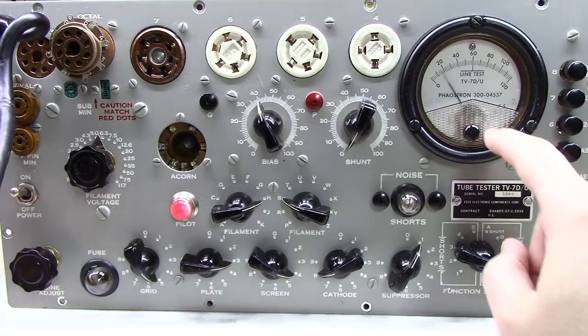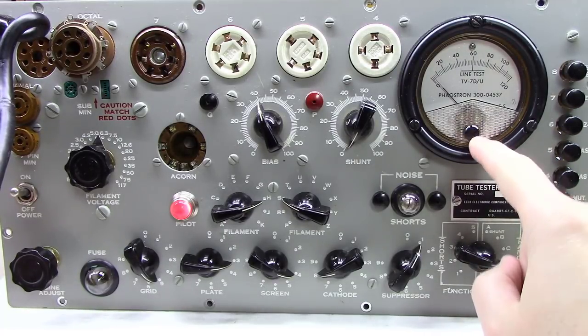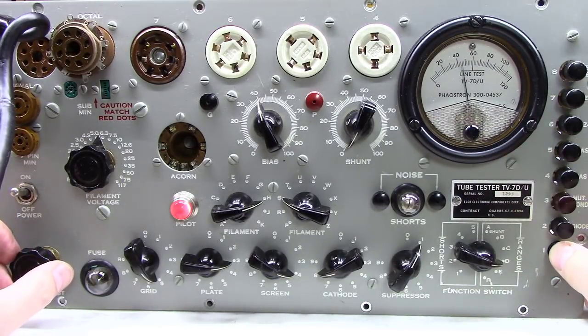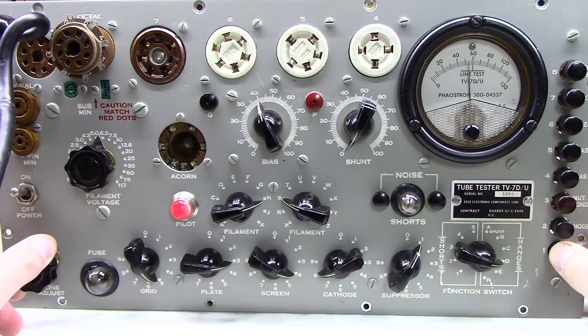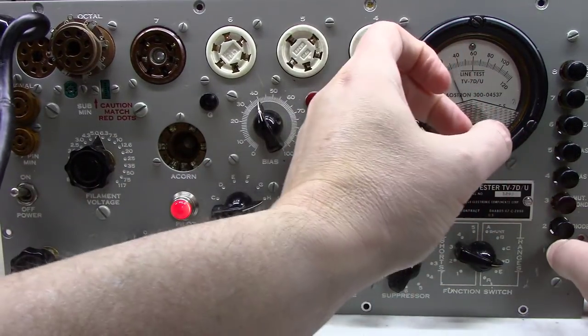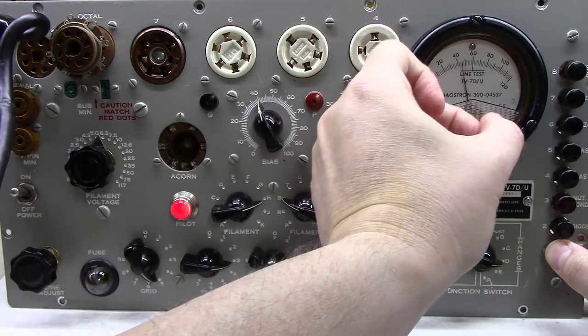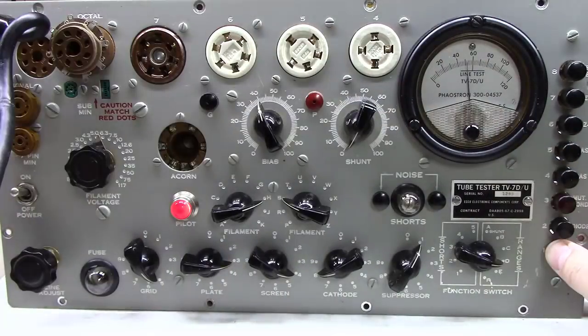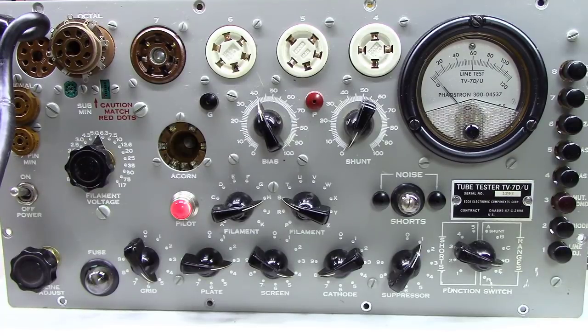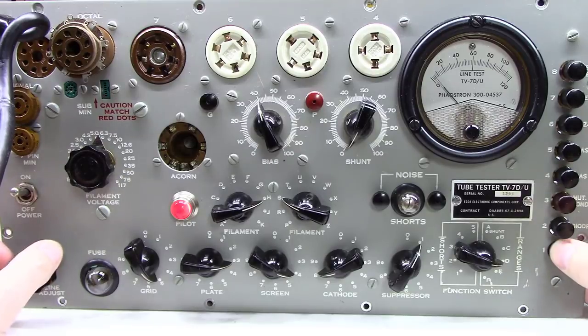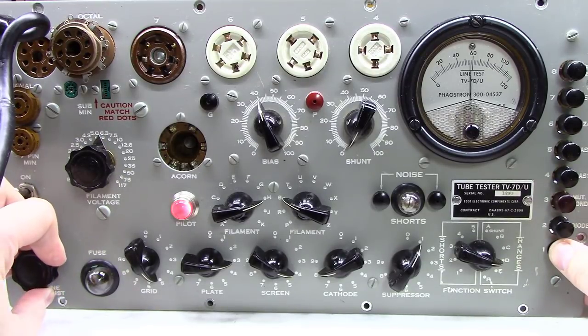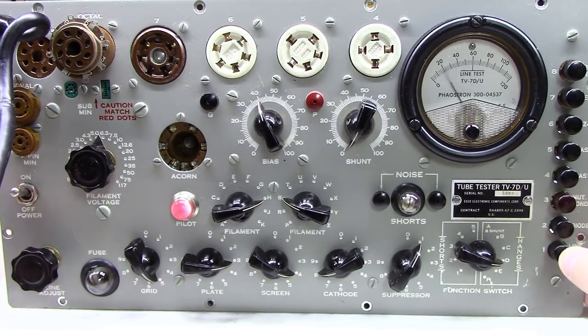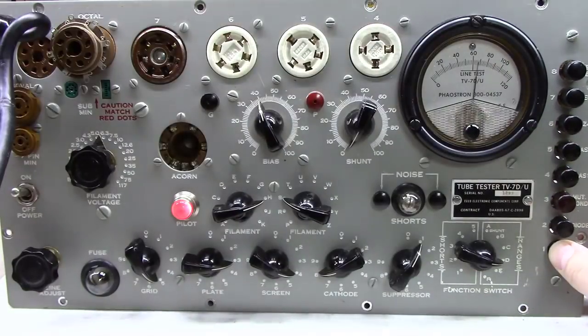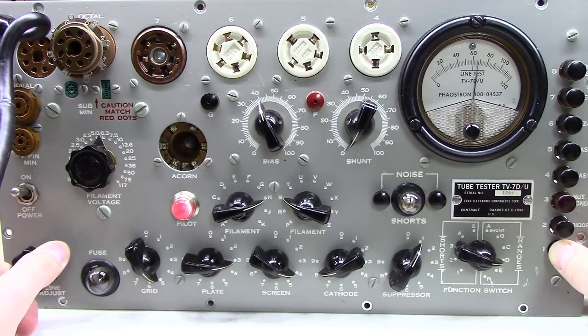And what this is called is a sticky meter pivot inside, and these things over time just get kind of worn out. Watch this as I thump it and bring it back. Now look where it's at. You have to thump the thing to get it to go where it's supposed to go. Now over time that becomes extremely frustrating as you're trying to use a unit, because you're trying to do your line adjust. Okay, I think I got it right there on 60, and then you bring it back and it's sitting there on 60, but then you thump it a couple times and oh, it's not on 60, it's up there on 68.